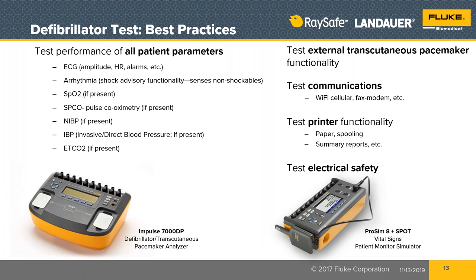For other defibrillator analyzers, you may need a stopwatch in order to run that test. And the test is, from the moment you push the charge button on the defibrillator until the ready tone sounds, how long did that take? There's a specification in the standard and in the manufacturer's service manual procedure that tells you what that pass-fail criteria is. And so you need to make the measurement, and that charge time test is part of what we do. We also do the synchronized cardioversion test, and we do a series of output energy tests. For routine testing, like twice a year, normally we would just test with a 50 ohm load. And then, as I said, for acceptance testing or post repair or this clinical problem, then we do the extra load testing, unless the manufacturer requires those extra loads.